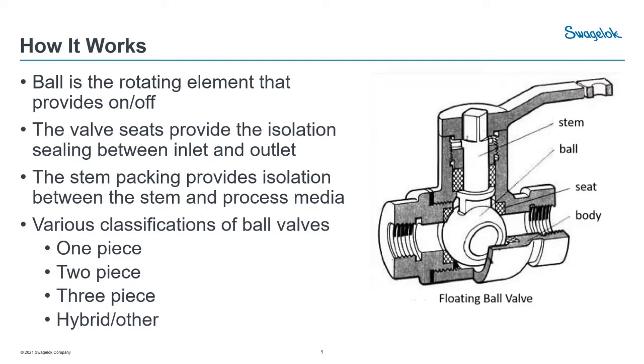How does it work? The ball is a rotating element that drives the on-off. This cutaway shows it technically in the off direction. When the ball is 90 degrees to flow, it's in the off position. The valve seats provide isolation and sealing between the inlet and outlet side. There's a ring-shaped seat, which is pretty common, and that seating material seals the ball. It's straightforward and easy to get a really good seal because everything is circular.